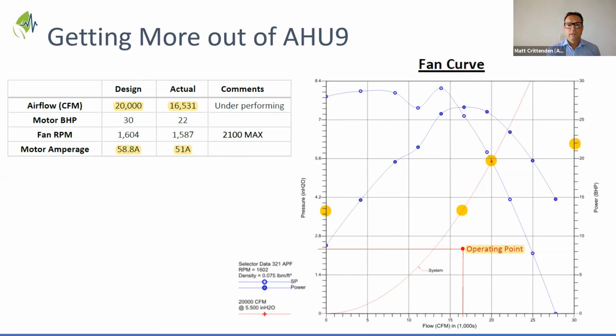So looking at those numbers and that fan curve, I would be the one saying I would not want to tap in any more from that unit. It's old. I don't want to take it out on the highway. I would leave it the way it is. If there's any way you can repurpose some of the air off of that system, that would be good. Look at maybe a department being served by AHU 9 that can now be tapped into a more robust system. That way, you could then divert more air from AHU 9 up to the other area, the emerge.